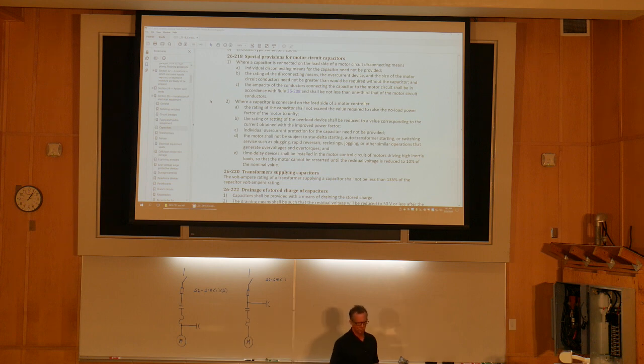All right, so let's read the rules, and we've got to be aware of what's happening here. So 26218 subrule 1 applies here, and it also applies here. Where a capacitor is connected on the load side of a motor circuit disconnecting means, an individual disconnecting means for the capacitor need not be provided. The rating of the disconnecting means, the overcurrent device, and the size of the motor circuit conductors need not be greater than would be required without the capacitor. And C, the ampacity of the conductors connecting the capacitor to the motor circuit shall be in accordance with 26208 and shall not be less than 1/3 that of the motor circuit conductors. All right, so what they're saying here, you size the motor circuit conductors as if the capacitor wasn't there.